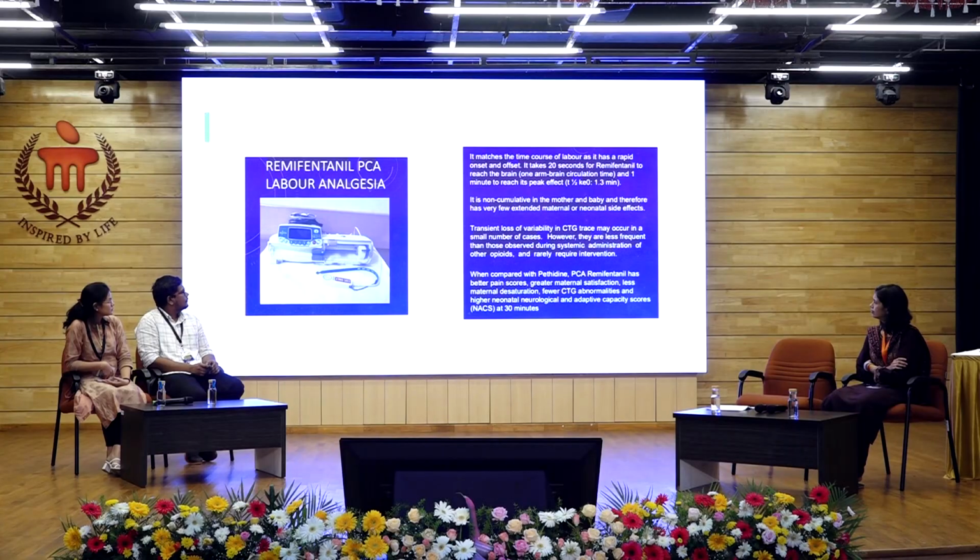The pump is a Fresenius Kabi Agilia SP pump. So it's a pump that does not allow you to deliver additional, there's no background infusion or clinician bolus options. It's only the patient can press it.